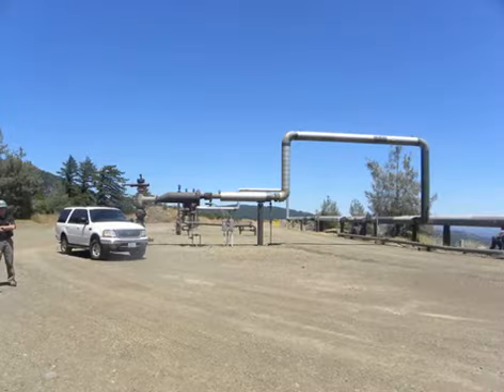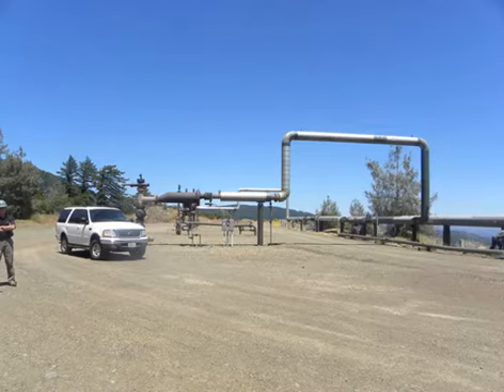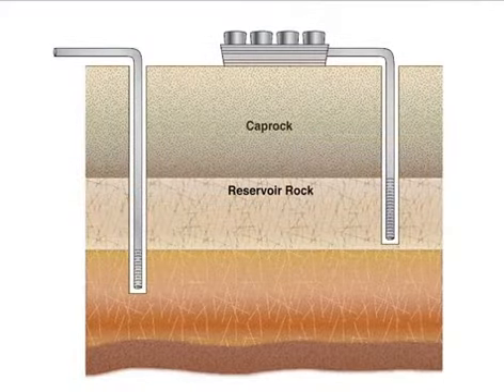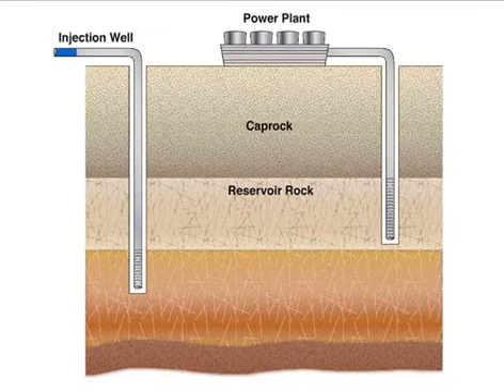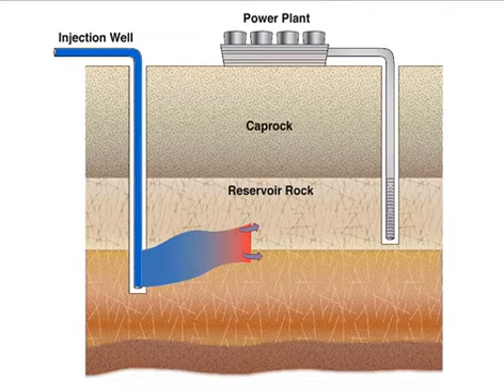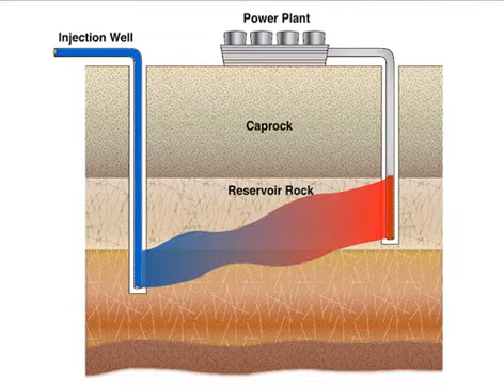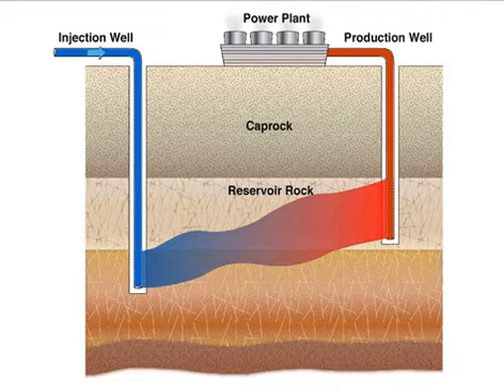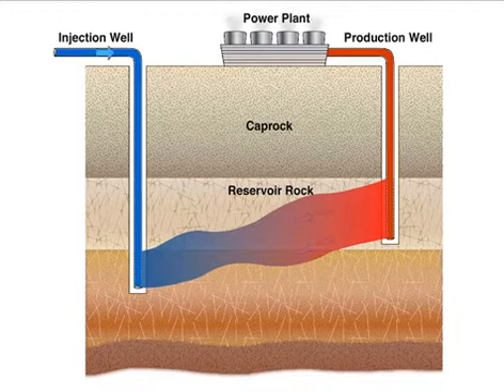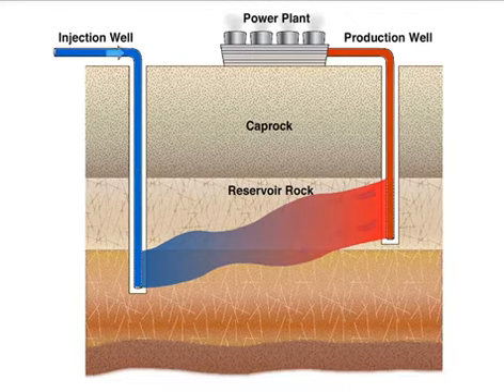In this shot, there are 2 production wells and 1 injection well. This is an animation of the injection and production process. Cool water is flowed into an injection well, typically with depths of 8,000 to 10,000 feet, and into the geothermal reservoir. The fluid is heated by the hot rocks to the point that it becomes steam. The steam flows through the fractures and eventually is tapped by 8,000 to 10,000 foot deep production wells, which bring the steam to the surface and carry the steam to geothermal power plants through a network of steam lines.